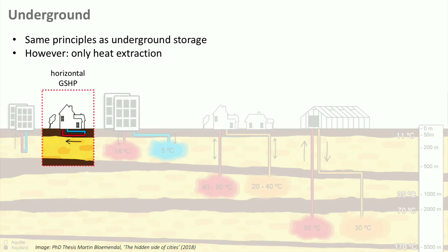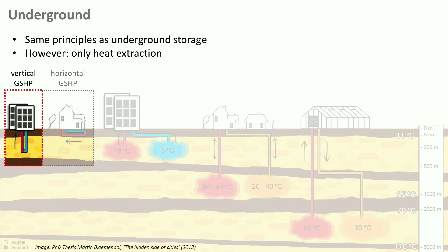Ground source heat pump systems use the top layers of soil, and there are two types. Horizontal ground source heat pumps use a network of pipes close to the surface — 1 to 2 meters — and although they are relatively easy to build, they are also more subject to seasonal changes. Vertical ground source heat pumps use one or more drilled shafts that go much deeper, up to 100 meters. This means a small surface footprint can deliver much more energy than a horizontal system, but drilling instead of digging is more expensive.